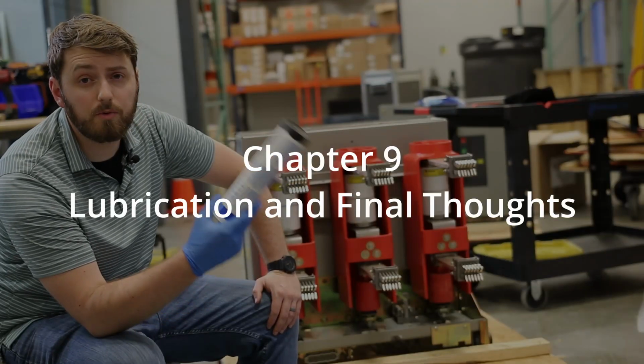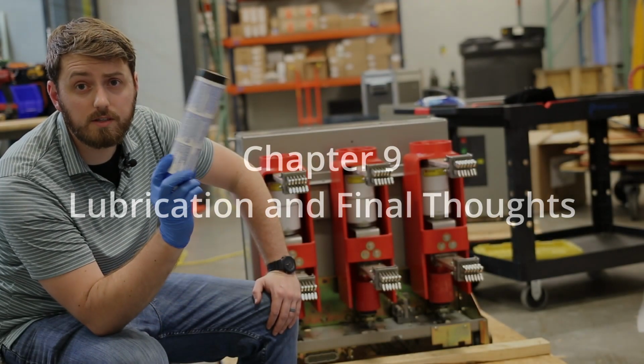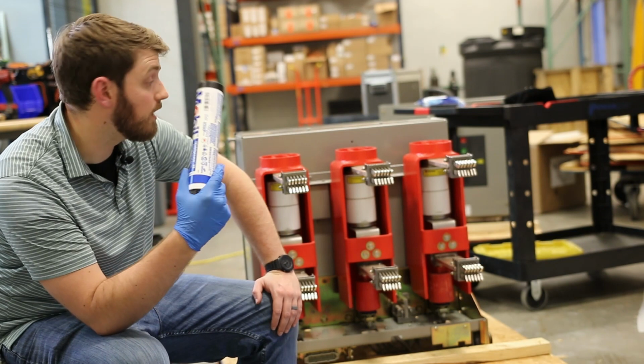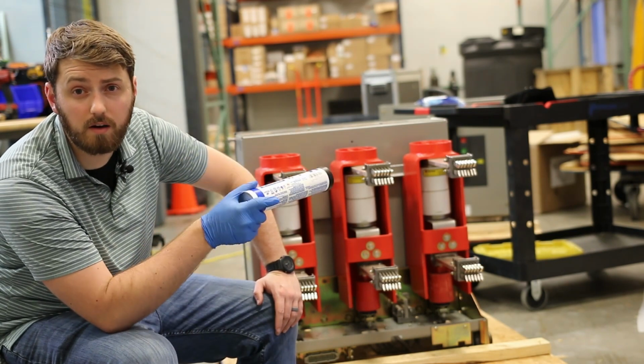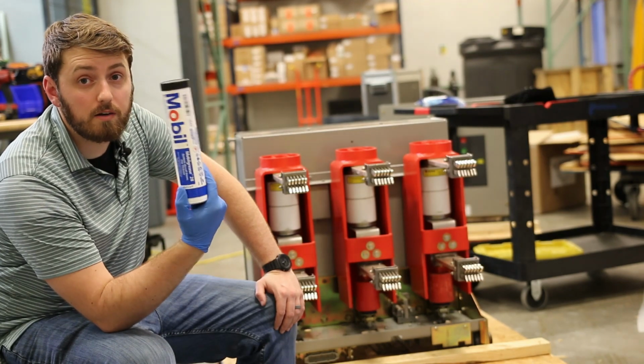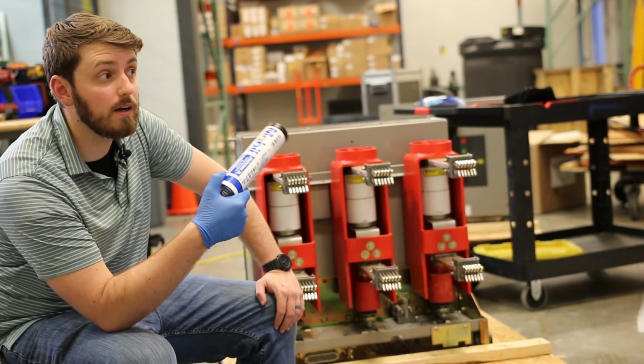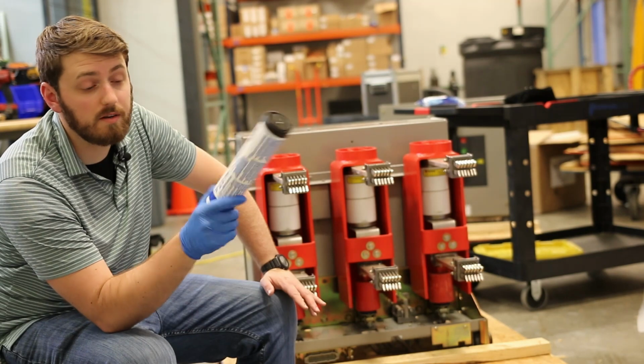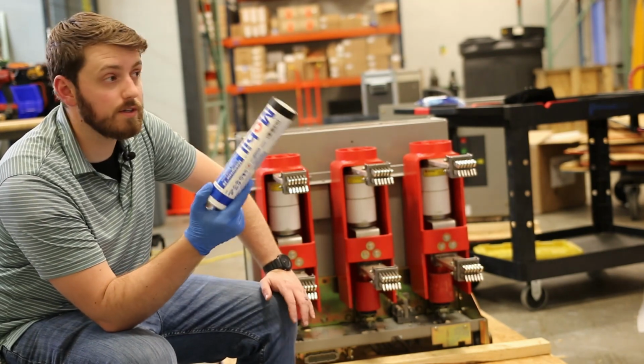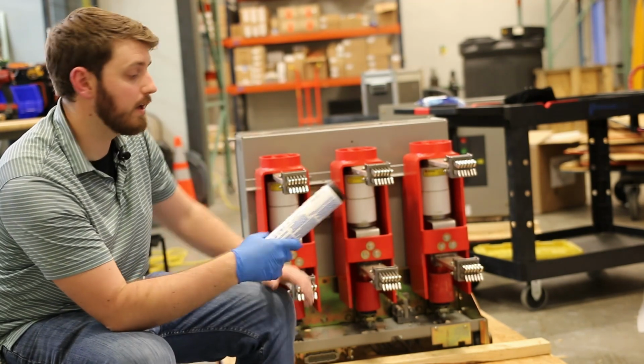The last thing we need to do before we stick this thing back in service is put some grease on the stabs. I've already greased up the inside when they had the cover off. I'm not 100% sure if I filmed that. We're going to use the manufacturer recommended Mobil 28. This is really common stuff. You get it pretty much anywhere. Square D will sell you their own branded thing, but it's Mobil 28.